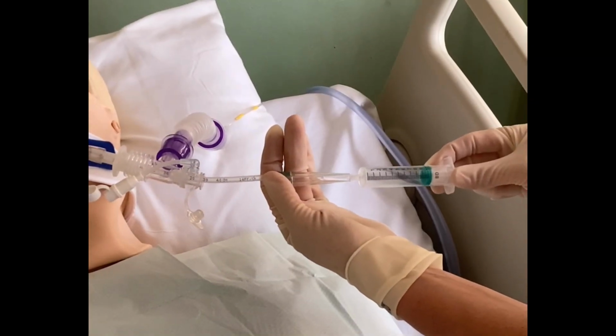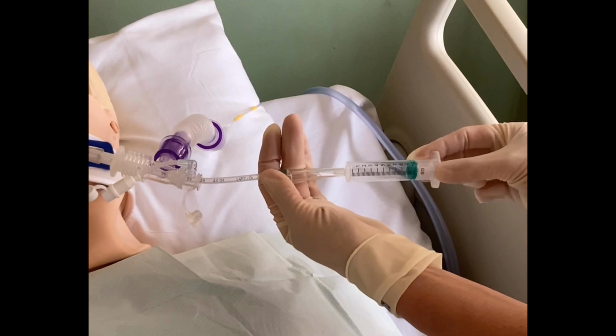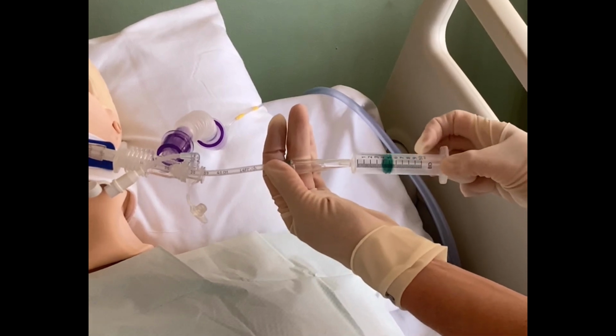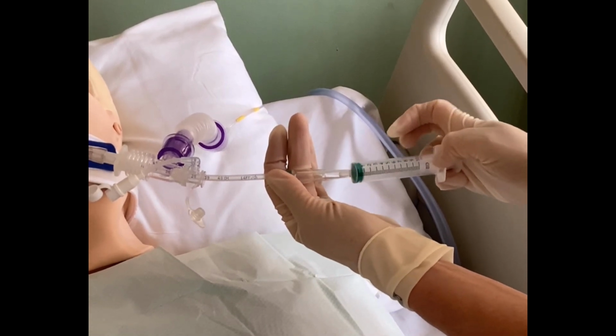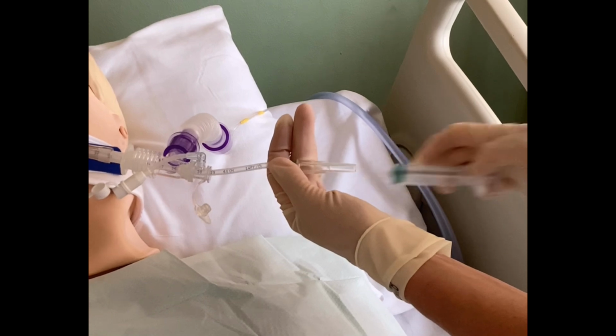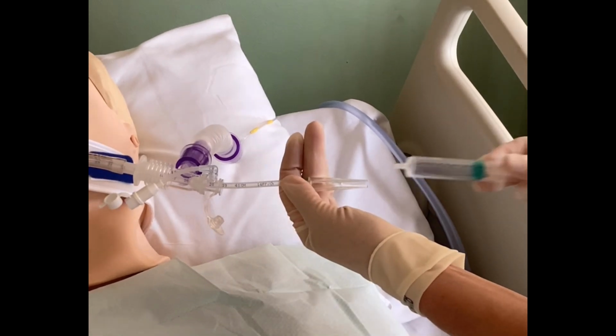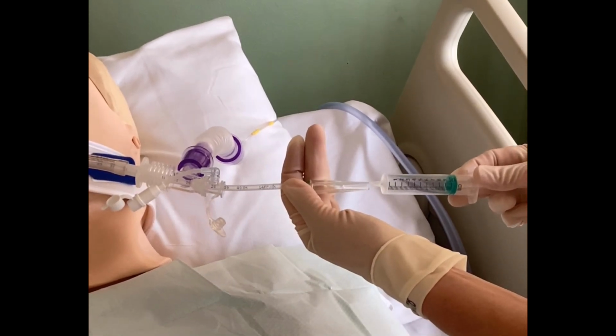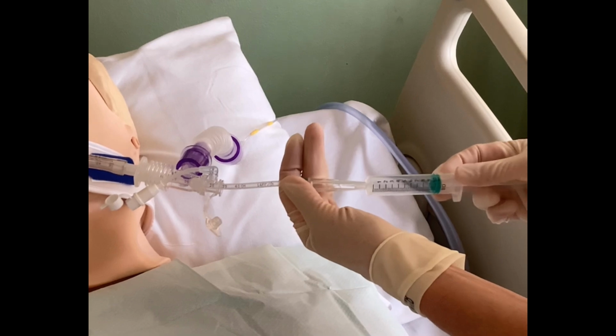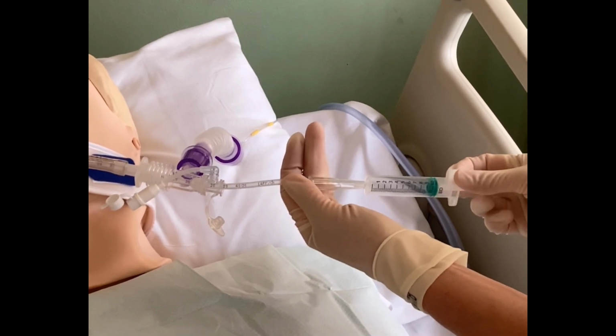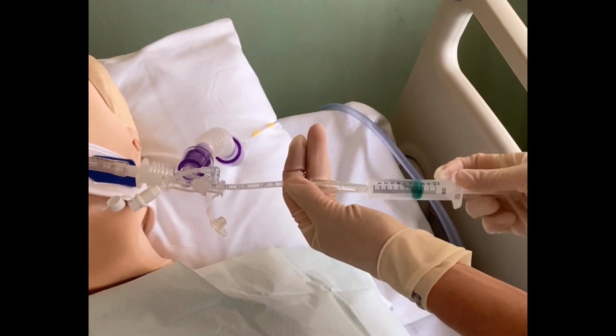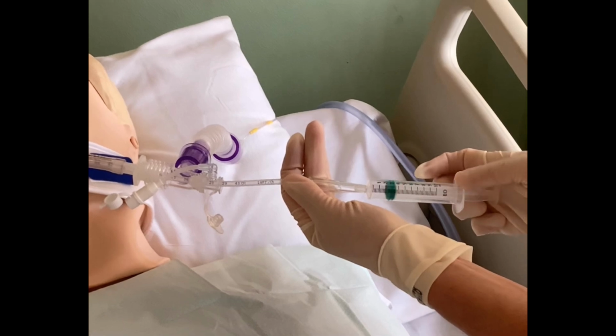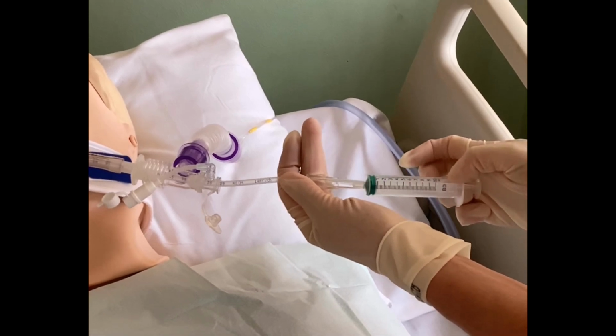Attach one syringe to the tip of the suction catheter and occlude the vacuum tip with your thumb. Instill the saline and repeat quickly with the second syringe, angling the catheter down to ensure the saline is fully instilled. At this stage, you may experience leakage around the catheter. The sample should not be affected by this, and you should still acquire an adequate sample.